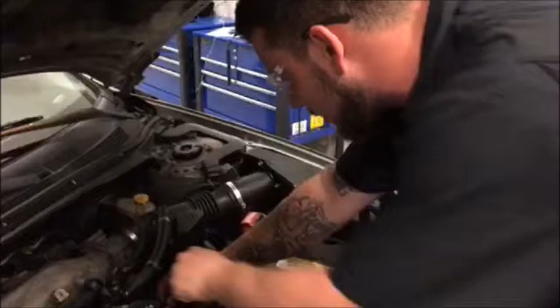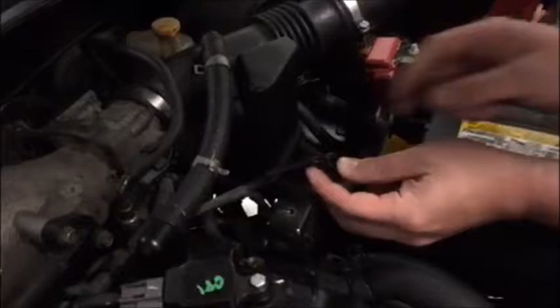Now on this one is a 3-wire sensor, and on here they have a red and green wire, which after we look at the wiring schematics, is the battery voltage or the voltage reference. The white wire is the signal, and the black wire is the ground.